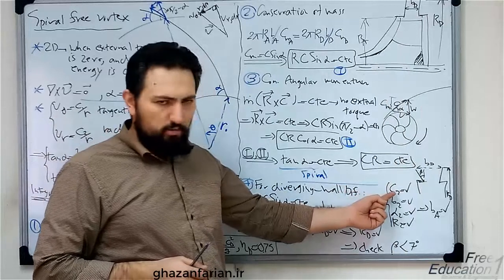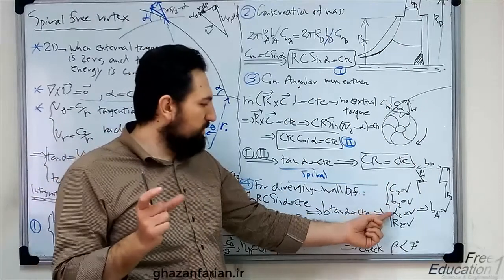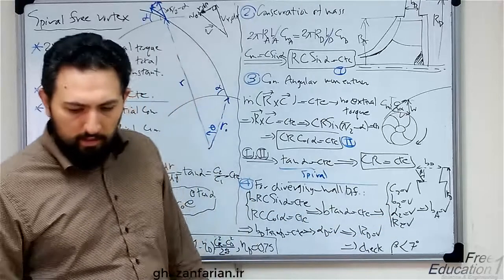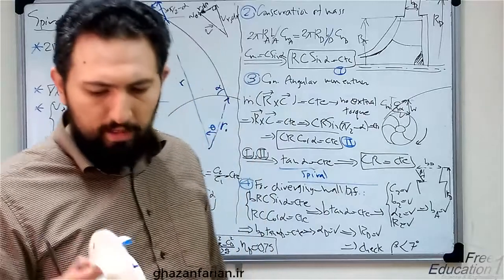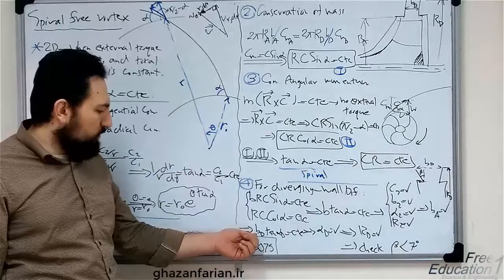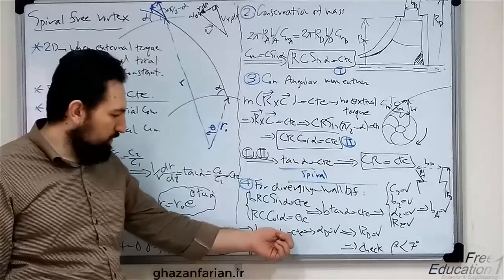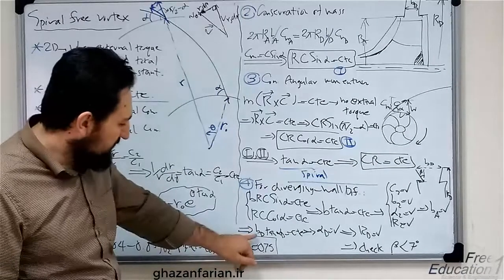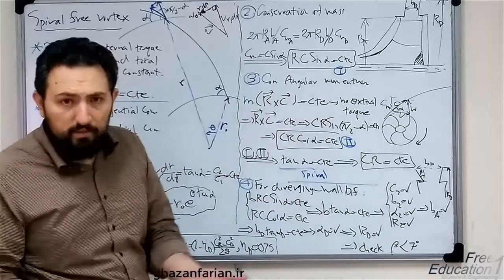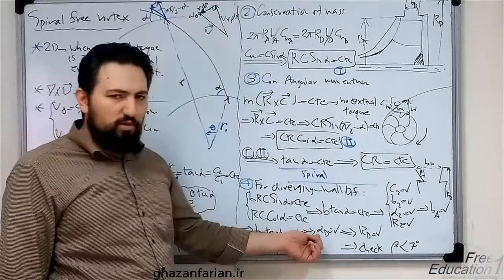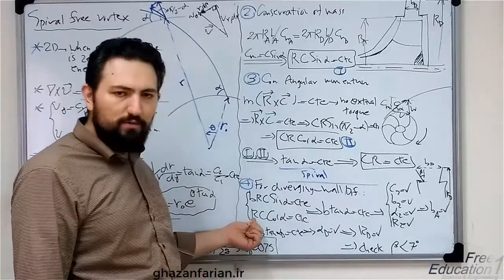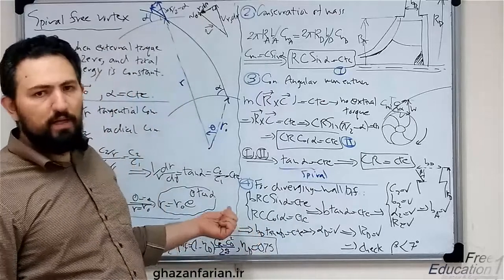You have already computed the velocity, the widths of the blades, the absolute angle, and the radius of the output of the impeller after completing the design process for the impeller. So you have the product of B sub D times tangent of alpha sub D, which should be constant. You have selected a value for B sub D based on the size of the diffuser, so you can compute the magnitude of alpha sub D and the radius of the output of the diffuser.